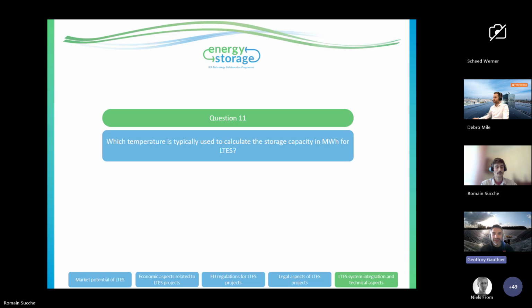And if you go slightly into overpressure, you can go up to 100, even up to 104 degrees in some specific designs, without having a specifically pressurized tank. So that's the maximum temperature. The minimum temperature is usually the return temperature plus a couple of degrees if you're coupled via heat exchanger.